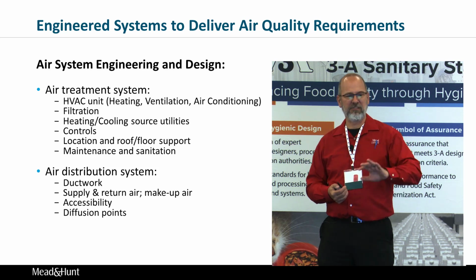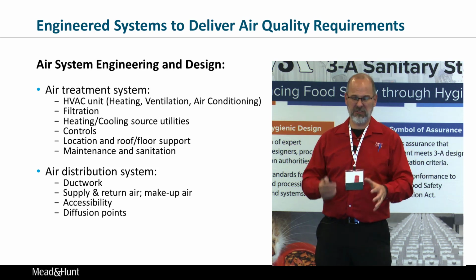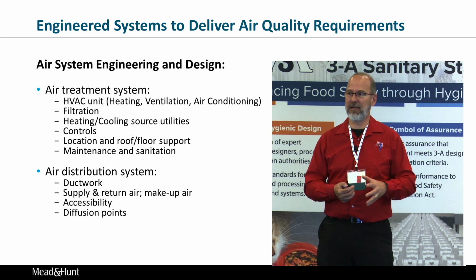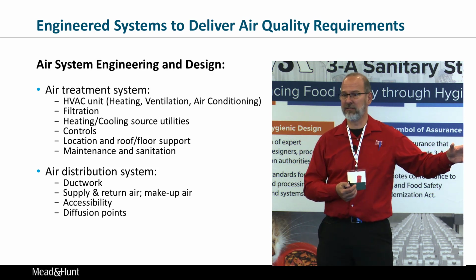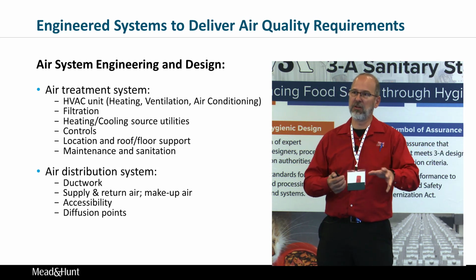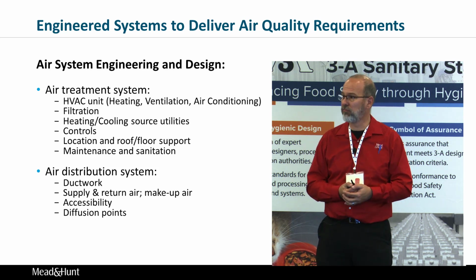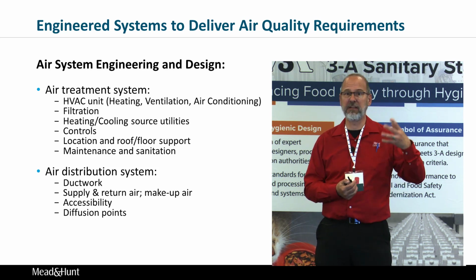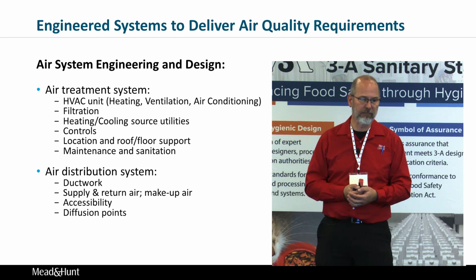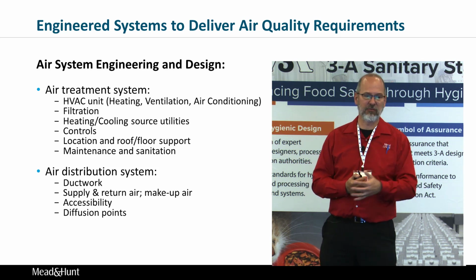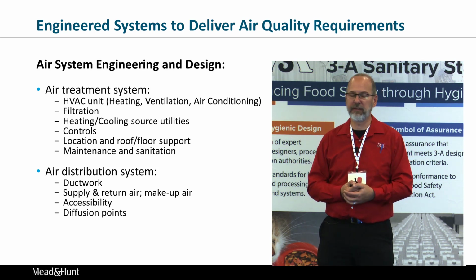And that's the first part. The second part is the air distribution system. Once you condition the air, you treat it, you've got to get it out to the spaces where it's needed, because you almost never put these large air handling units inside a process room. So usually they're in an interstitial space or on the roof or a mechanical room somewhere. So you've got to get the air to the space. Well, how are you going to do that? You're going to do that with ductwork typically.